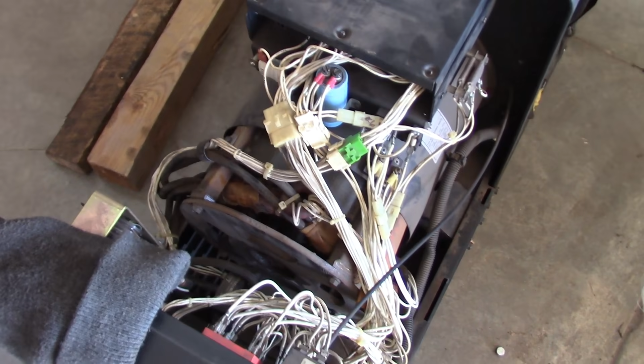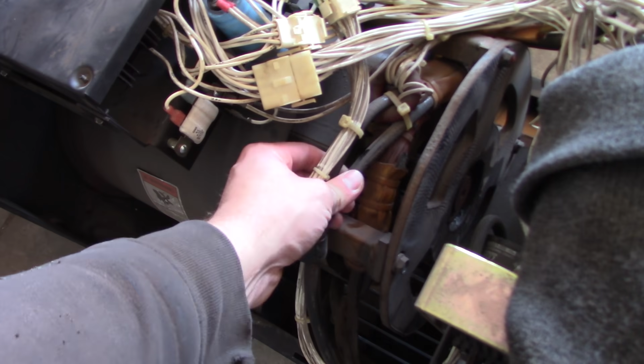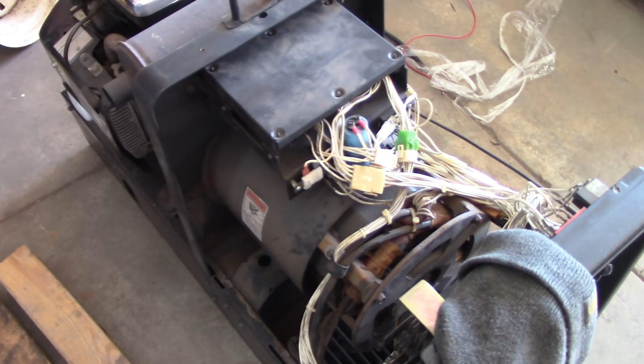He said he was just welding with it and it stopped - no output or low output. He sent it to an authorized Miller repair facility, and they checked it and found a short in the stator winding. Lead 73 is supposed to be shorted to ground somewhere, so we're going to check that real quick. He just wanted a second opinion about it before he moves on. I guess the stator winding is not available from Miller - it's discontinued, and the cost to have it rewound exceeds the value of the welder.